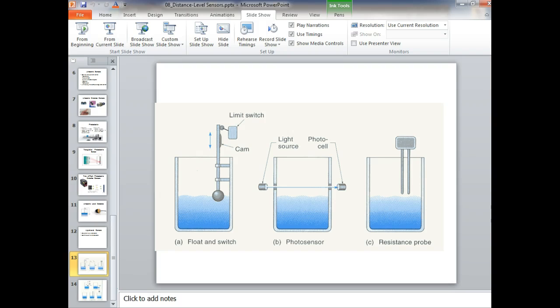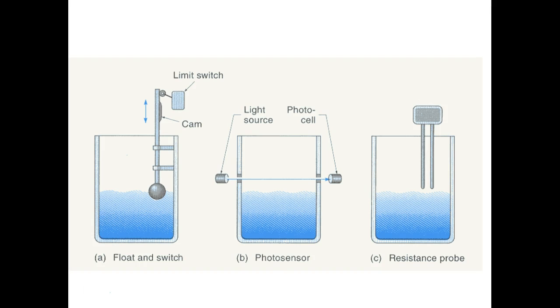So basically that's it. With solid state sensors, it's no big deal. You just use a solid state sensor to pick up a relay, right? And then use the contacts off the relay to control as much as you want. Then we could use the contact off that relay to pick up another relay, right, if we needed tons of contacts. But these guys right here are pretty straightforward. The ones we're using would fall in which category? Would be this guy right here, except instead of having a limit switch, we're using a magnetic.